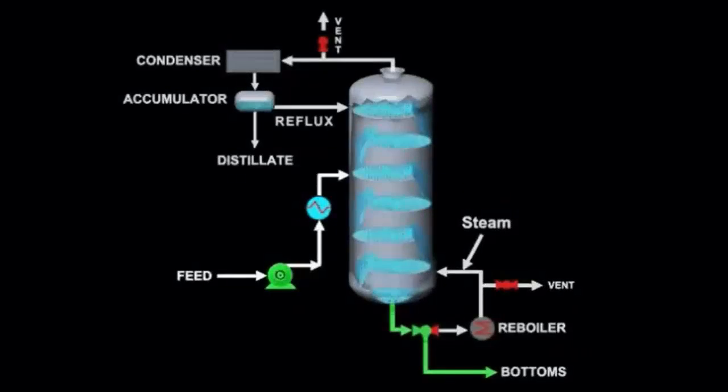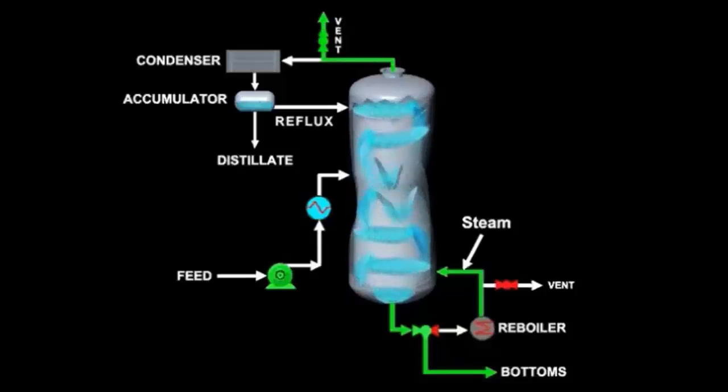If steam is added directly to the column already containing cold water, rapid condensation can occur, creating a vacuum inside the column. This practice should be avoided.